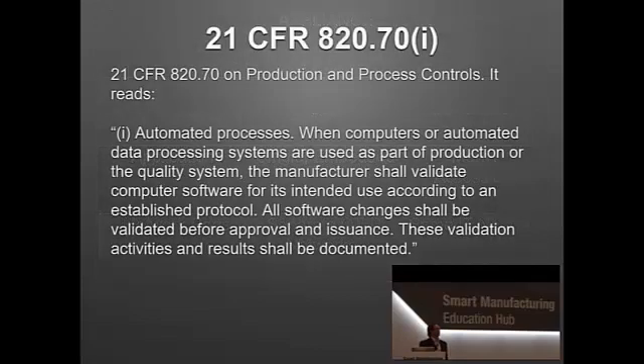Now to the FDA software validation pain. So we have learned through our end users that we're a black box to the FDA. And what does that mean? When software is added to the production and process control, you have to meet 21 CFR 820. All of it needs to be documented. You have to validate the software for intended use for the established protocol, and any of the software changes that occur, security patches, new features, they have to be validated also. All of the validation activities have to be documented as well.